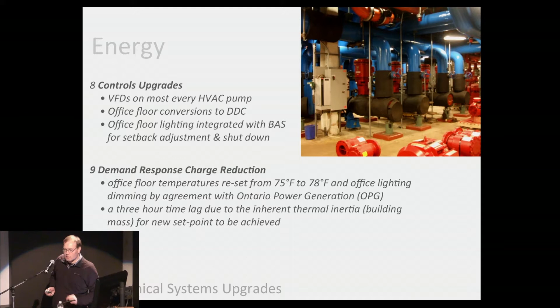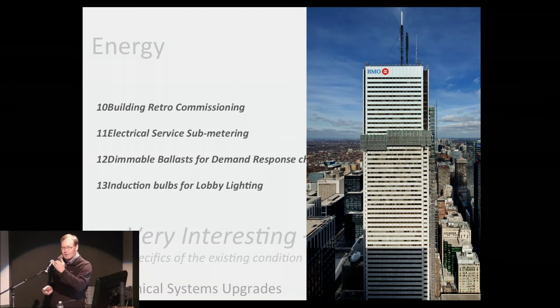I found this very interesting. And this came out of this whole LEED EBOM study. And then we did retro-commissioning. I just want to indicate, there's a whole regimen of stuff that we did on the interior of the building, including saving water. Now, one last really important thing that we discovered. When we put in the heat recovery chillers, we're saving the operation of the cooling towers. And there are 2 huge cooling towers at the top of the building. They use a lot of water. And because they're so high volume, there's a percentage lost in evaporation.